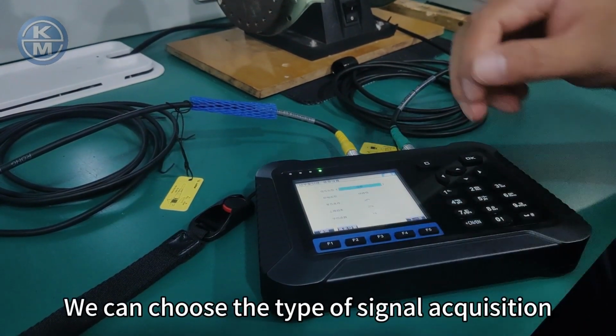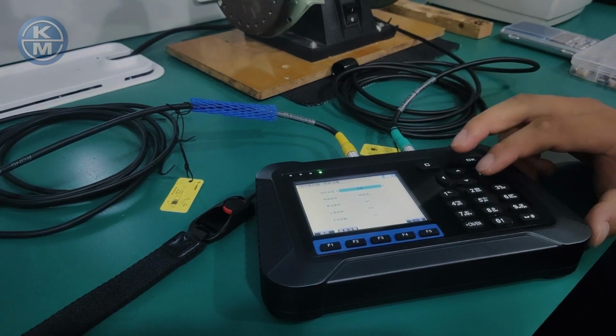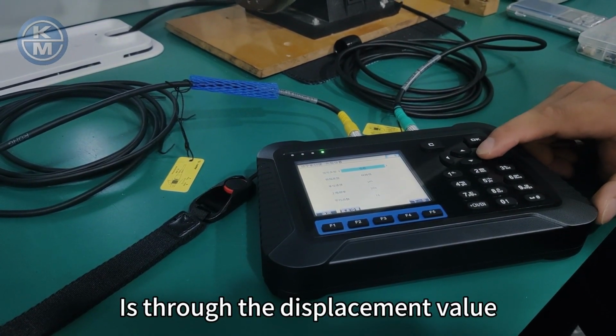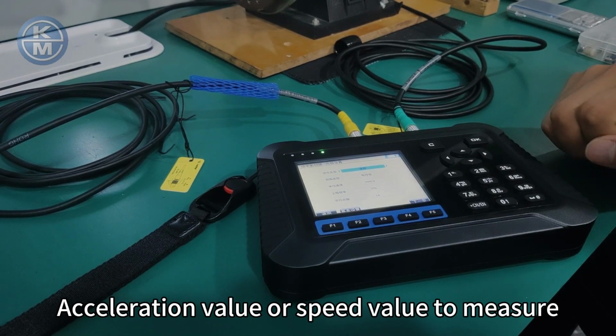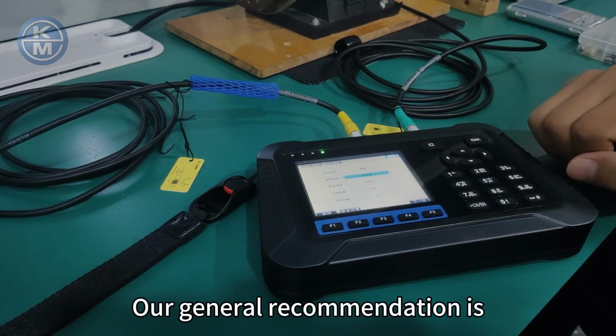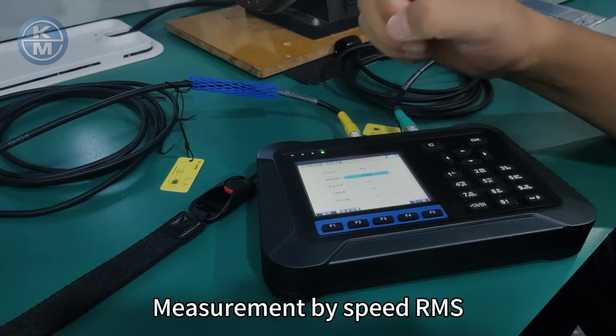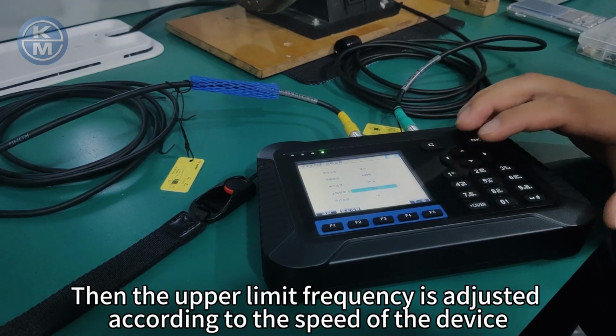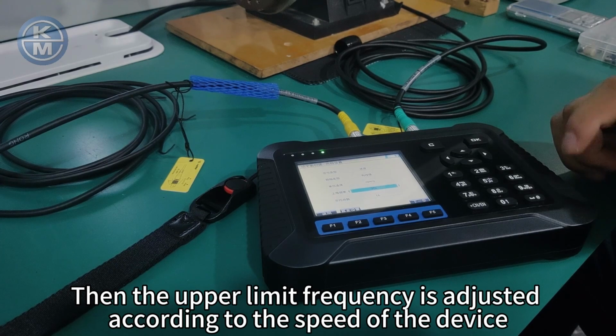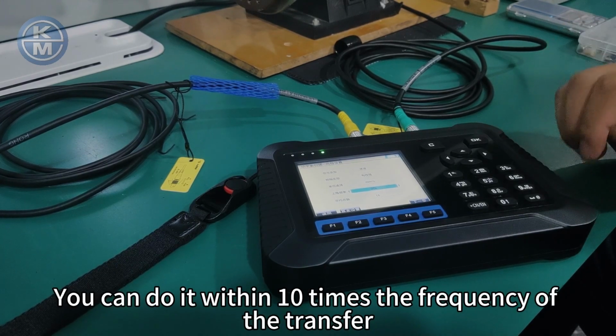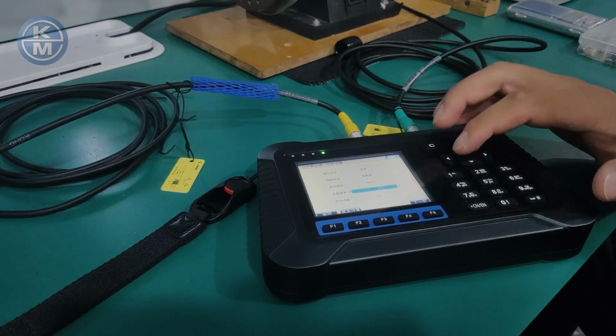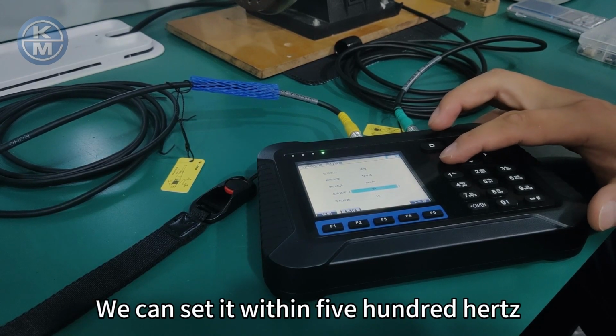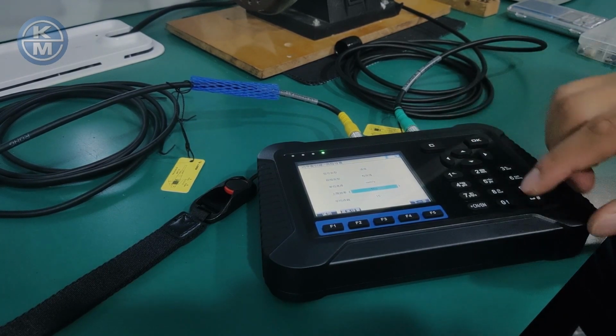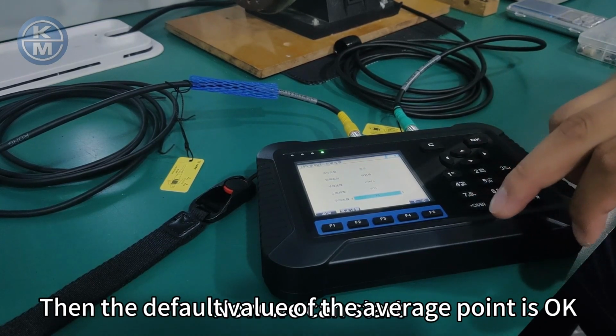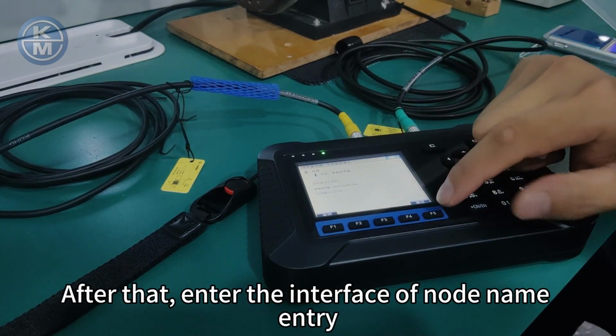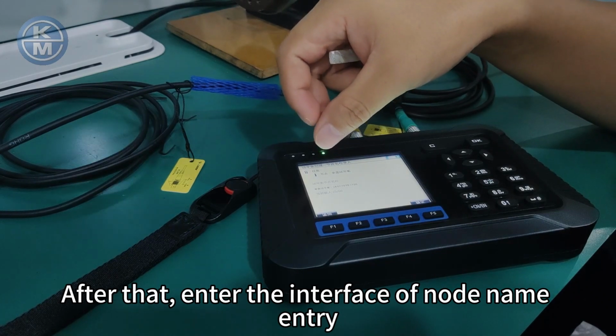In the advanced settings, we can choose the type of signal acquisition, whether to measure through the displacement value, acceleration value or speed value. If it is 3000 RPM, our general recommendation is measurement by speed RMS. Then the upper limit frequency is adjusted according to the speed of the device. You can do it within 10 times the frequency of the transfer. This is 3000 RPM, the transfer frequency is 50 Hz, so we can set it within 500 Hz. Then the default value of the average point is OK. Now we can start. After that, enter the interface of node name entry.